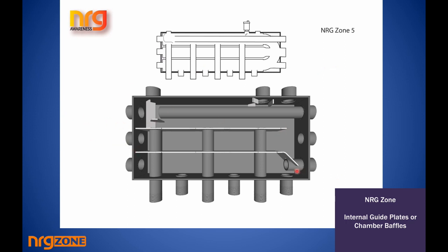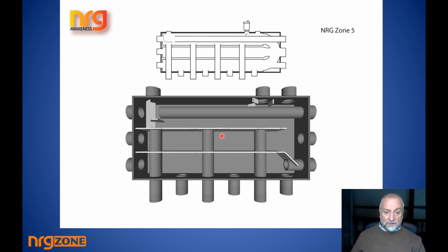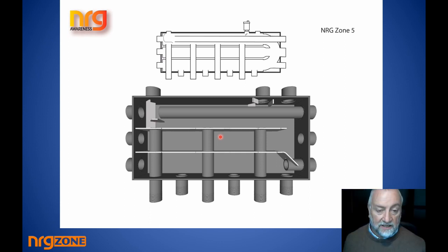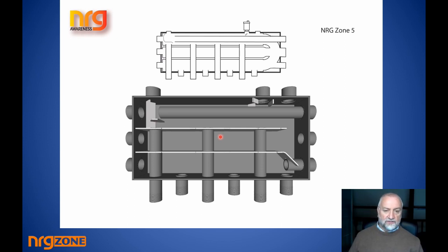Obviously there's a left and a right hand side, but remember we've also made obscure shaped units to suit particular purposes, and in that situation, if you ever required that kind of a strange device for a very awkward boiler house or whatever, we'll create a shape to suit whatever you want, and we'll create flow chambers, return chambers, whatever. So instead of being stuck with a very awkward boiler house, you make the manifold suit the boiler house, and then you pipe directly onto the manifold, and you've just slashed the labour content and the confusion aspect of what would otherwise be a very typically ugly looking boiler house that you're trying to figure out. You get your work done inside the manifold. So you can see there's a similarity with the two.